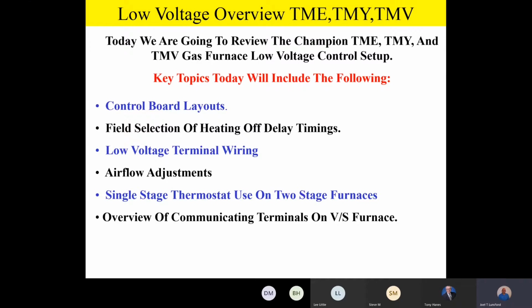Key topics, okay. We're also going to be talking about field selection of heating off delay timings. Now, team, one of the things about our furnaces, and this is universal across all of our Champion furnaces, the factory on delay timing is set at the factory, but the off delay timing, in other words, how long the fan continues to operate after the call for heat goes away, that is field selectable, and we're going to show you where to find that on the boards.